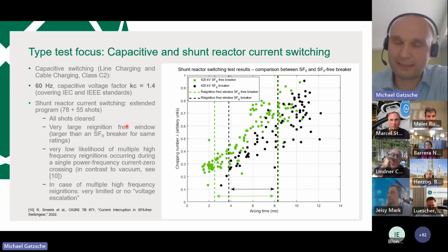That is generally, of course, an advantage of gas circuit breakers compared to vacuum, this very low likelihood. And what we have seen is that with the SF6 free technology, the likelihood is even lower than with SF6. So I think really good performance, really good ratings that we could achieve here with the circuit breaker.